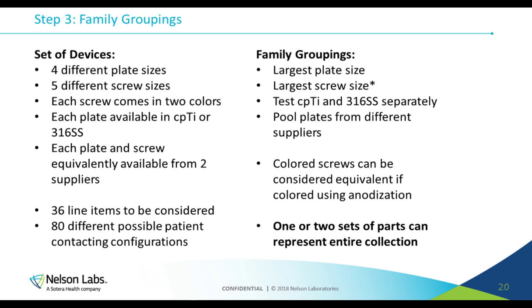So that's how we go through and assign or decide whether or not we're going to do a biological test or if we're going to try to do a written evaluation or if chemistry will help. And we go through and evaluate the data that's available to make all of those calls, trying to balance, we're considering, of course, the safety of the device to patients first, and then also considering, okay, what do we believe will be acceptable to a regulator against the burden of doing the testing itself.